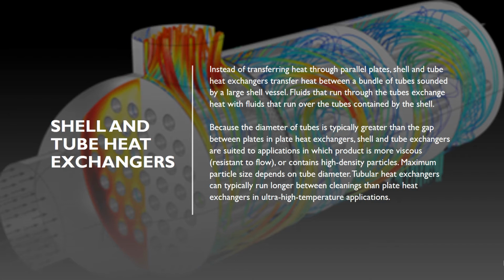Shell and tube heat exchangers. Instead of transferring heat through parallel plates, shell and tube heat exchangers transfer heat between a bundle of tubes surrounded by a large shell vessel. Fluids that run through the tubes exchange heat with fluids that run over the tubes contained by the shell.